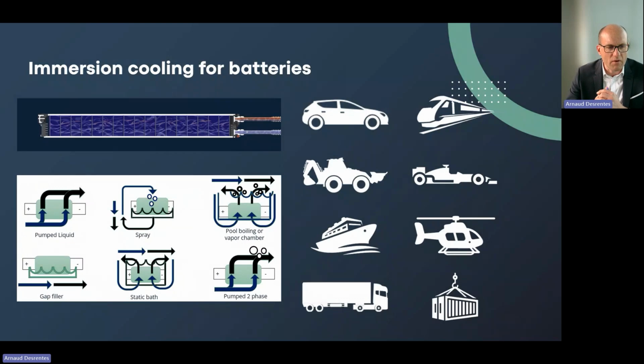If you go down to the graph, you have what we call gap filler. So you remove some glues or some thermal pads, and you transform them into liquid. You use liquid in terms of thermal pads. Then you have what we call static bath. It means that you have liquid inside, for example, a module with no circulation, or inside a complete battery pack. And here the liquid is enclosed. You have no circulation. And the sixth one is called pumped two-phase. So you have a circulating liquid that transforms into gas when it's in contact with hot surfaces. These are just 6 examples of various architectures of immersion cooling. So you see that immersion cooling is really wide. And you have the kind of domains that it can address on the right side.